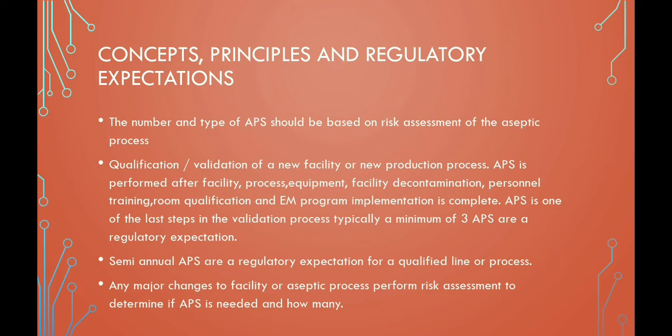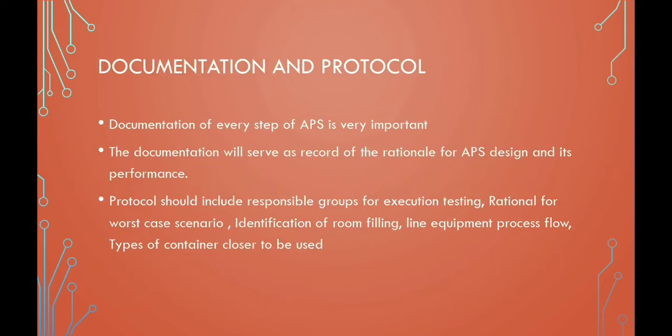Documentation is a crucial step for aseptic process simulation. It serves as a record of rationale for APS design and its importance. Documentation should include step-by-step instructions for performing the aseptic process simulation, acceptance criteria, results obtained, and any deviations. Documentation majorly includes the protocol and batch records. The protocol should provide the rationale for worst-case scenario and identification of room, filling line, equipment, and process flow.